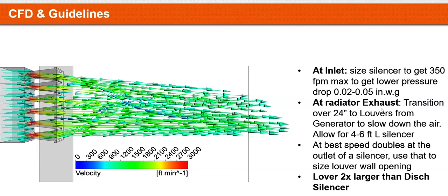At the radiator exhaust, you do want to add at least a 2 to 3 foot long transition from the silencer to the louver. The reason being is if you look at this velocity profile out of a CFD analysis, even though the airflow is coming out at a nice 900 feet per minute from the radiator exhaust fan, into the silencer internals, from any manufacturer, the largest free area you're going to get is around 50%. And that's going to give you your best pressure drop. The larger the free area, the better the pressure drop inside the silencer. But because it's a 50% free area, what does that do to your airflow speed? It doubles it at the very least.